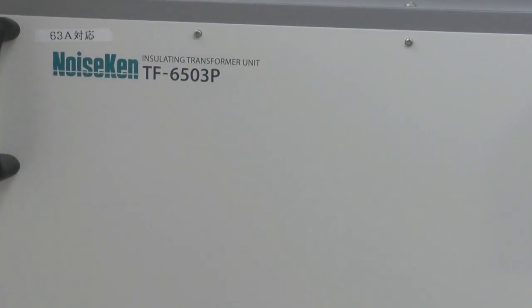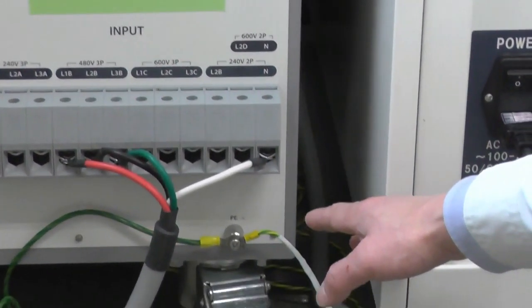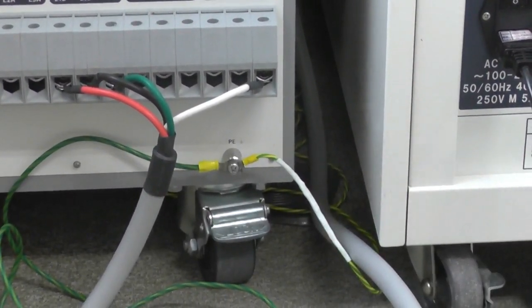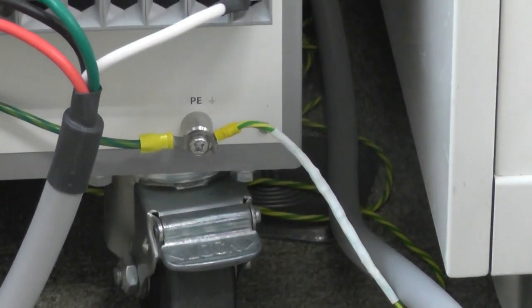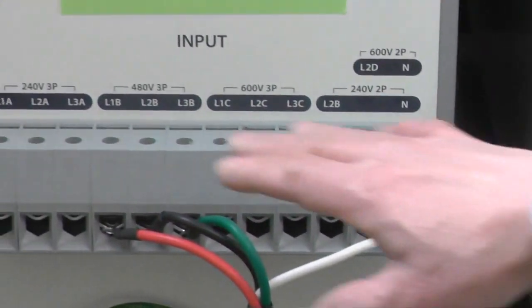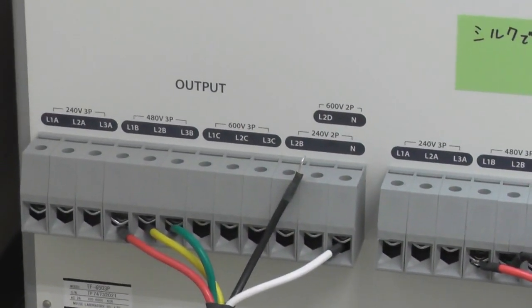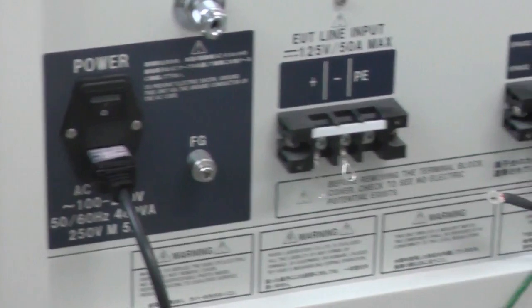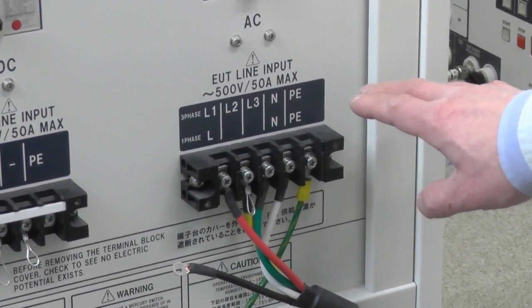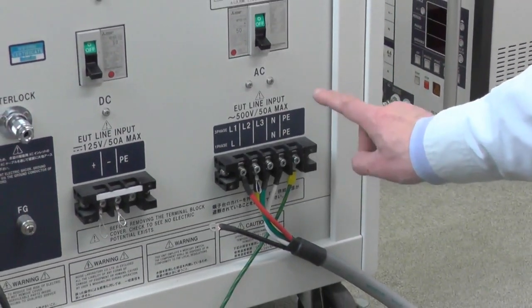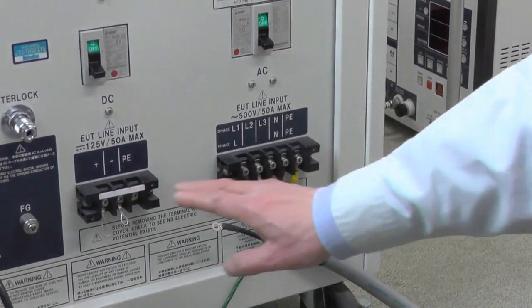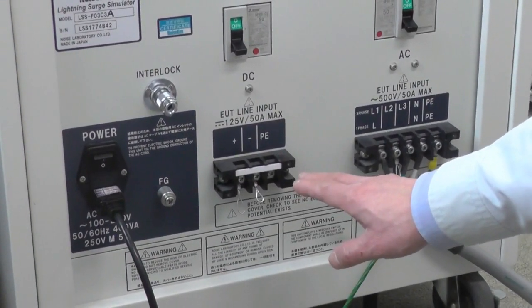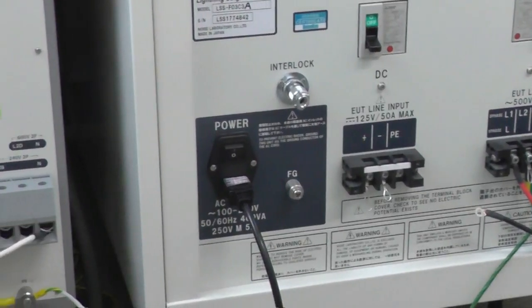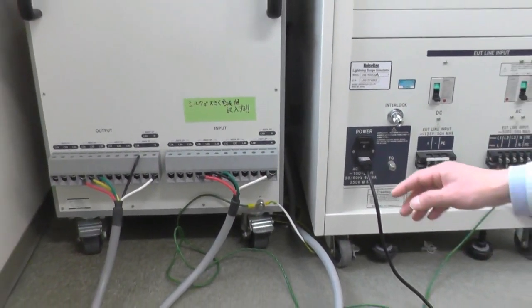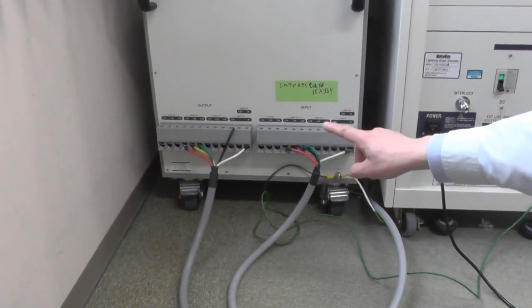TF6503P. First, for safety, be sure to connect the PE terminal to the protective earthing terminal of the test room with the PE cable to ground it. Next, connect the appropriate AC line cables to the AC line input and output terminals. And here, this is the line input terminal of the lightning surge simulator. Use the line input cable to connect to the AC line input terminals for AC power supplies or to the DC line input terminals for DC power supplies. And here is an example of the connection of the 3-phase 5-line 480 volts connection.